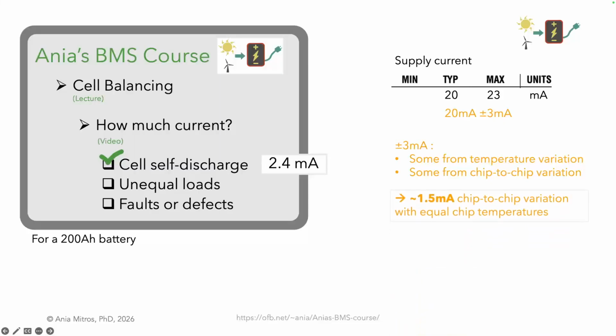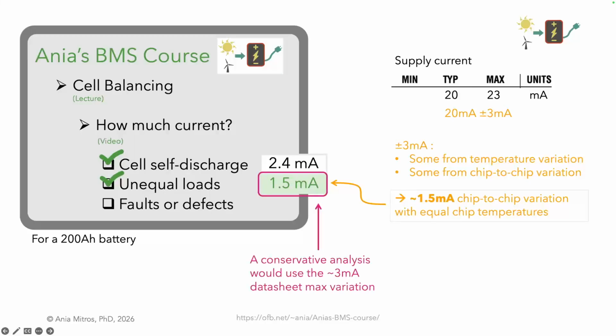In practice, then, we might expect the supply current variation to be about half that 3 milliamps in the datasheet, around 1.5 milliamps. I will put 1.5 milliamps into our table. However, that's not a rigorous number. A conservative approach would stick with the 3 milliamps from the datasheet. Before we go on to faults and defects, let's discuss one caveat.